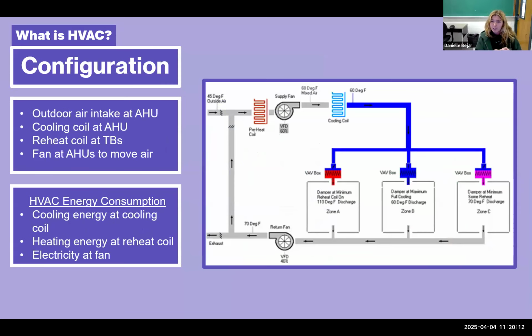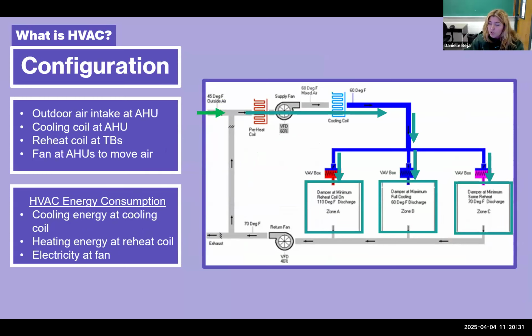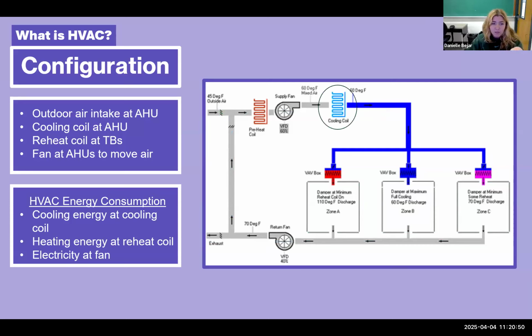Now looking at the overall configuration, here's a schematic of an HVAC system. To orient ourselves, we have our outdoor air intake. Then the air will go through the cooling coil at the air handling unit, through the ductwork, through the reheat coil at the terminal boxes. And then the air is in the zones. The zones are the rooms of the building, for example. This is where the people are. And then the air goes through the return duct. Some air gets released as exhaust, and the rest of the air will cycle back through the system. The fans are what is responsible for moving this air around. As for our energy consumption, we have cooling energy at the cooling coil, heating energy at the reheat coils, and then electricity at the fan.